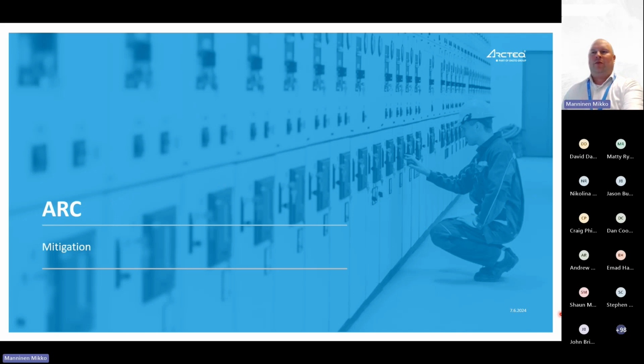Then the third step would be arc mitigation. This is something that Emad and David mentioned earlier already: the duration of the fault, arc calculations, calories. They mentioned these words quite a few times. With arc mitigation, there is a certain magnitude of the fault always, which is very, very difficult to limit unless you do the design completely. You can change the protection settings on the relays. That is one way to do it, and it helps in some cases. But the real magnitude levels we are talking about when there's a high risk with arc flash cannot be reduced much with the settings.